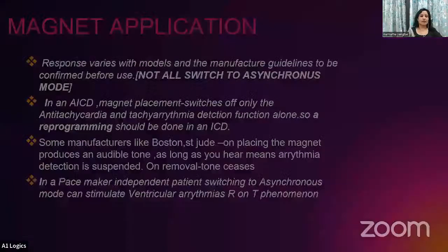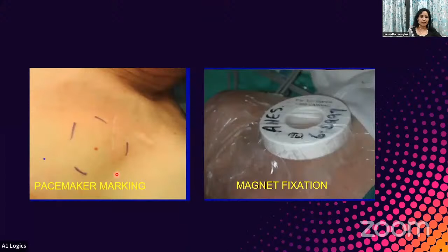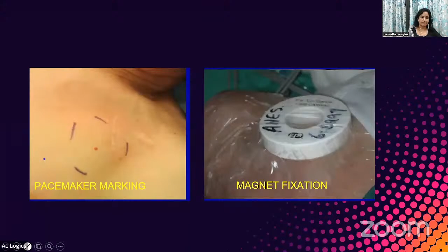Okay. So this is a picture showing first how to place the magnet. First, you have to palpate the edge of the pacemaker and mark it with a marker, and then place the magnet exactly over that and tightly tape it with the adhesive plaster. There should not be any gap between the magnet and the skin. Like that only you have to fix the magnet during the intra-op period. During the magnetic application, you have to take an ECG before applying the magnet and also after the magnet is removed, to make sure it is changed to the asynchronous mode.